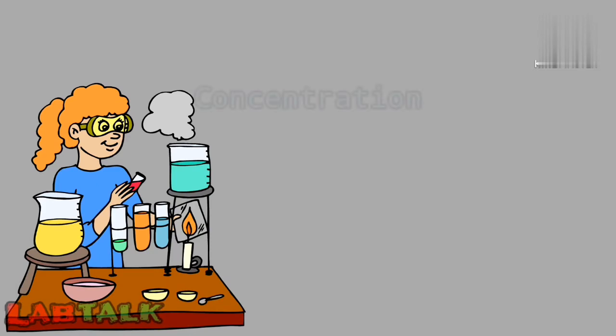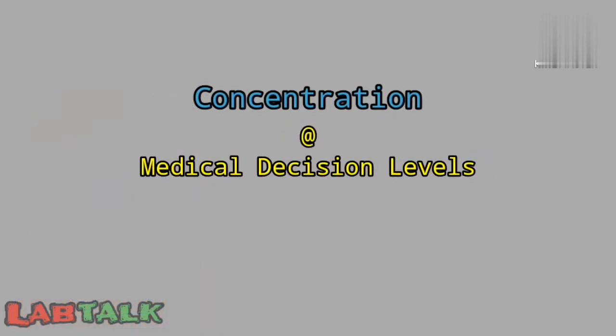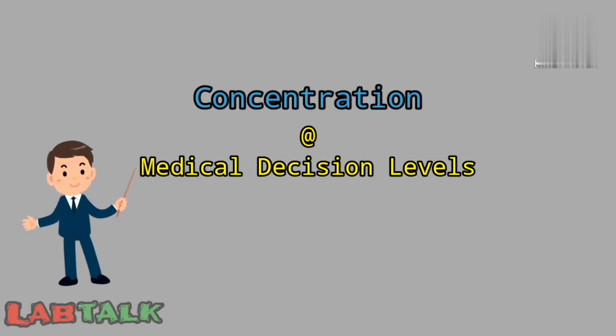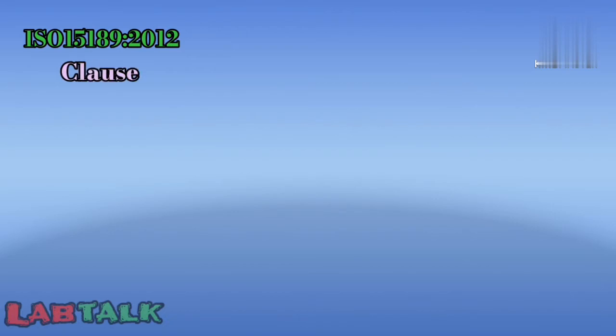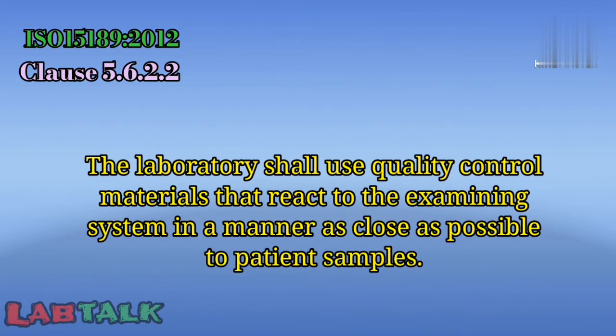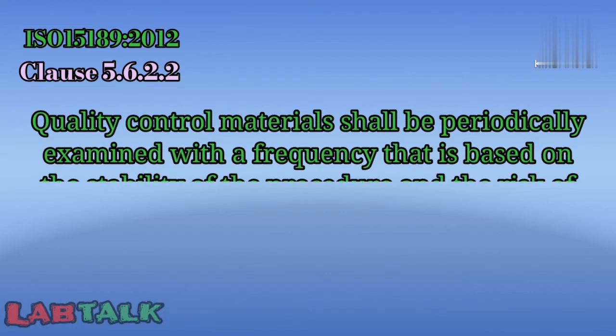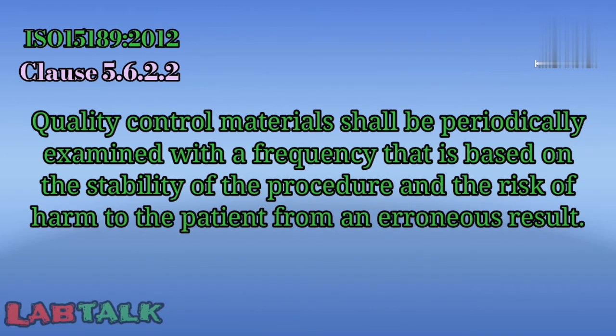Control material contains analytes which are determined by the laboratory, ideally at concentrations where decision limits are required for medical action. As per ISO 15189:2012, clause 5.6.2.2, the laboratory shall use quality control material that reacts to the examining system in a manner as close as possible to patient samples. Quality control material shall be periodically examined with a frequency based on the stability of the procedure and the risk of harm to the patient from an erroneous result.